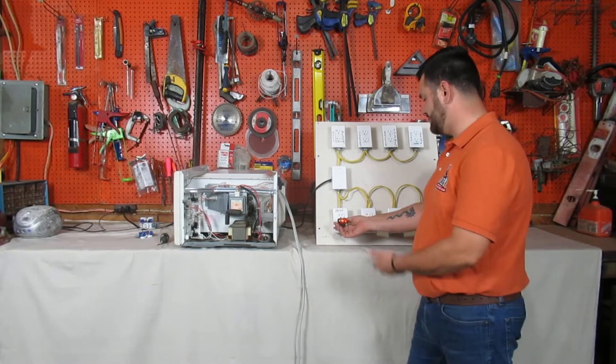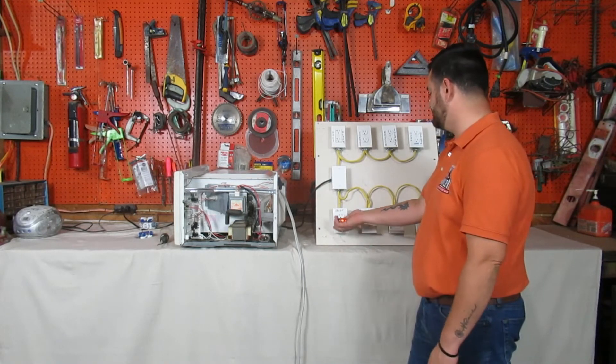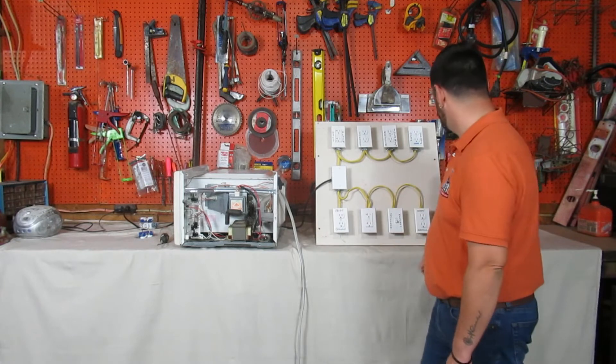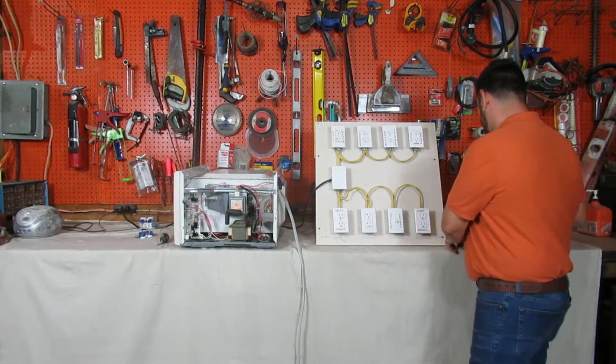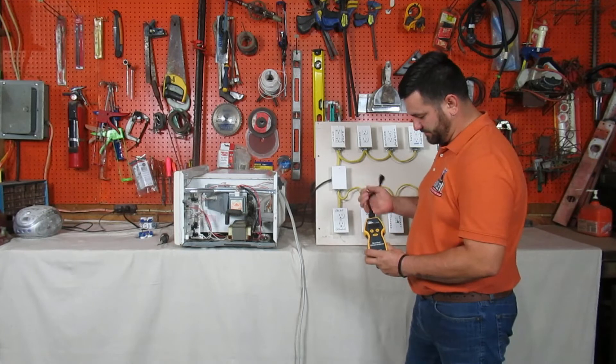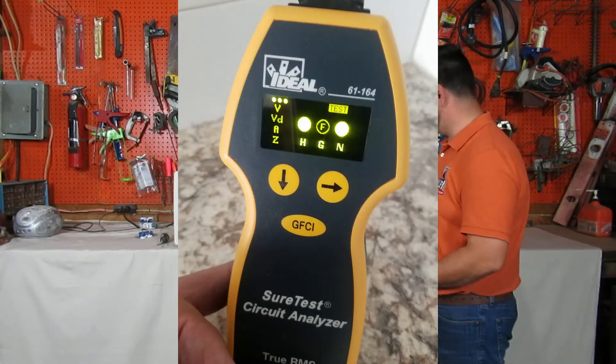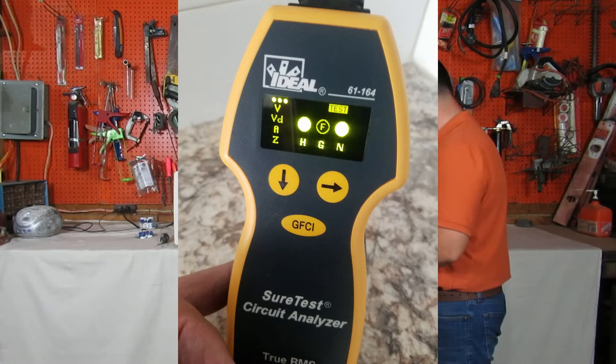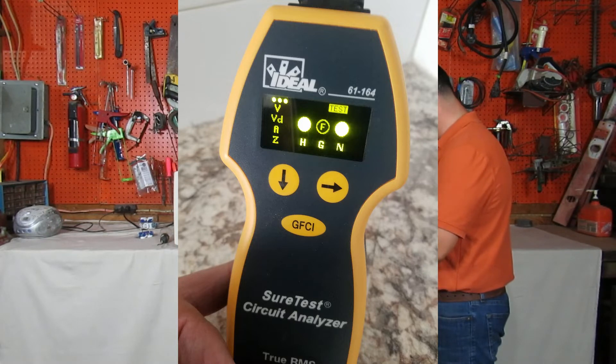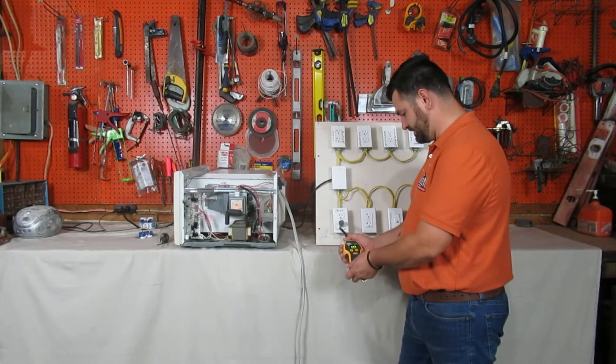But if you were to plug in this sure test, this $400 device that we use, a lot of home inspectors don't use this, you can get an accurate reading on whether the outlet is truly grounded or not. There it shows we have a false ground on this one.